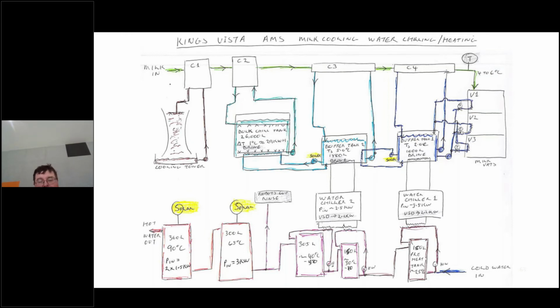At the same time, they're also heating our hot water, preheating our hot water. So you see the cold water comes in from the side. First one, it's getting to nearly 30 degrees at the moment. The next one's getting to 40. Next one at the moment is hitting about 55. And the last 2 are electrical, which we get up to. So you see there's not much left to get to 65, 90 degrees by the time it goes to the robots. There's the greyed out area there.